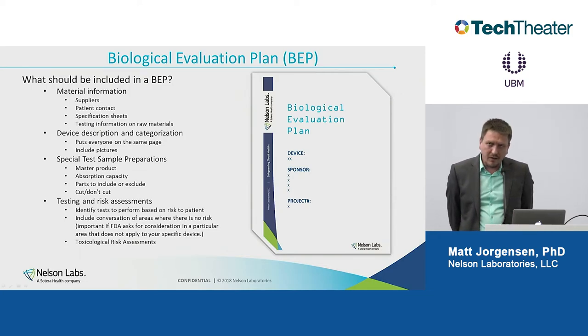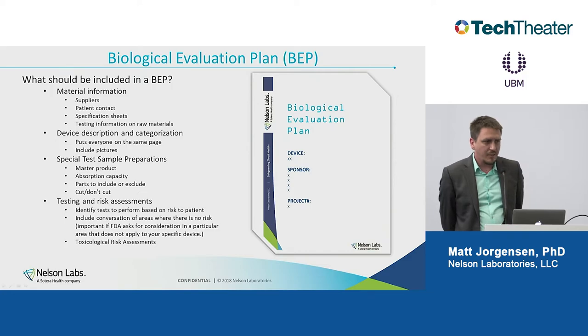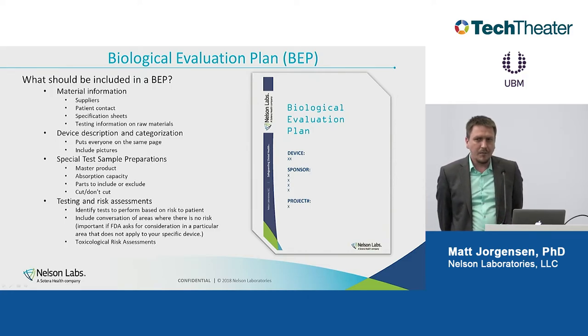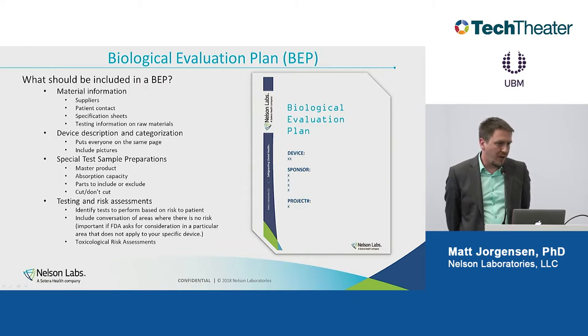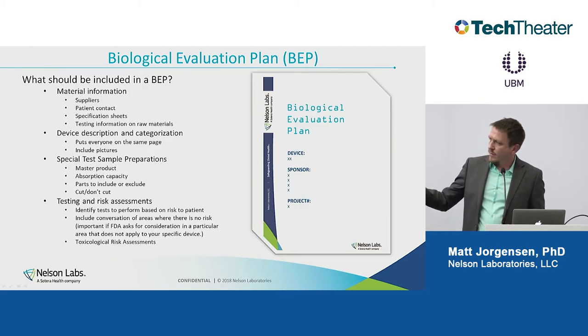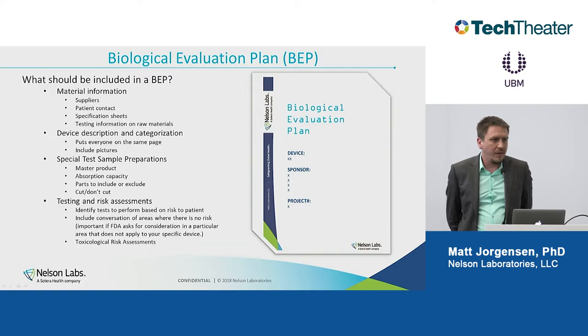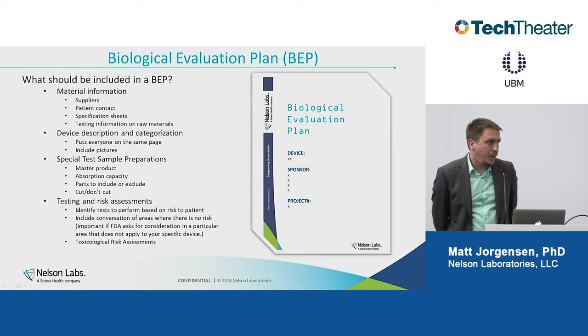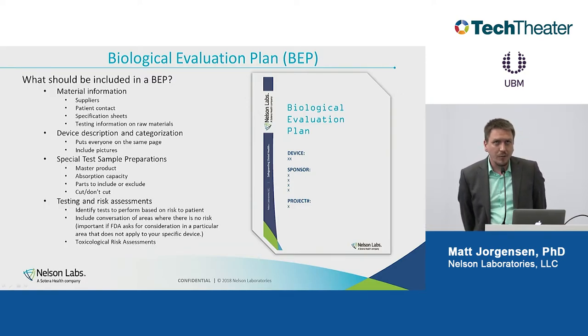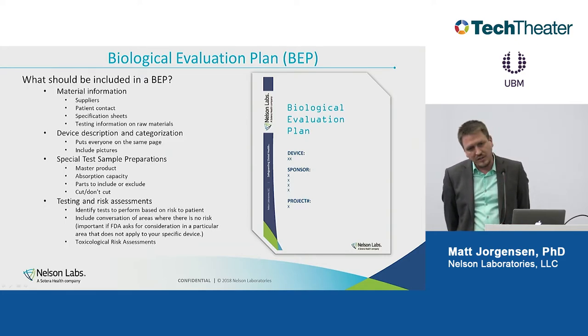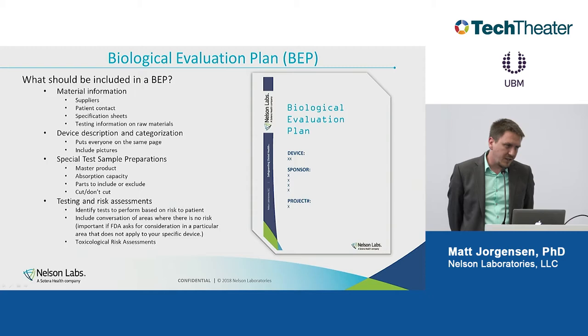The use of a biological evaluation plan, especially if you're going to go through a pre-sub or a Q-sub with the FDA, can be a really powerful tool. There's a little bit more effort upfront, but it gives you the ability to take on a little more regulatory risk because you know you're going to check it off with them before you go too far down the path of evaluation.